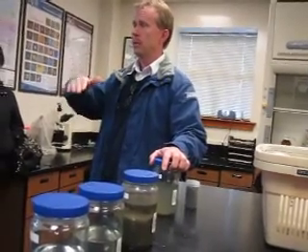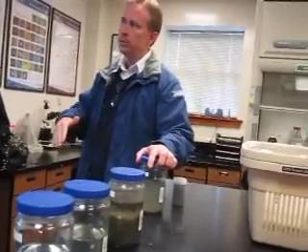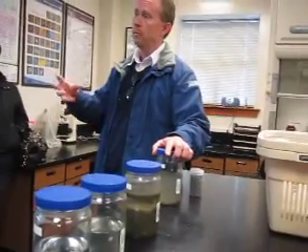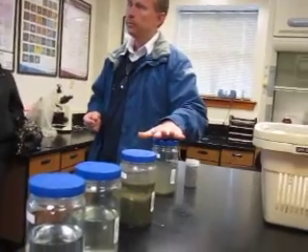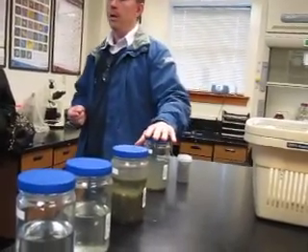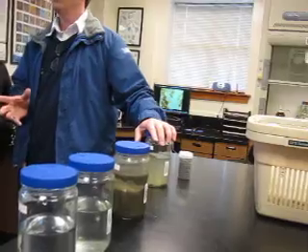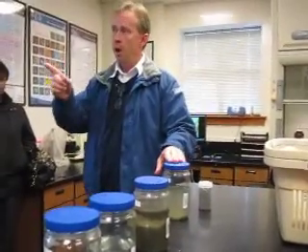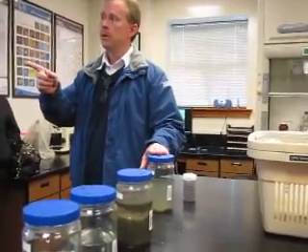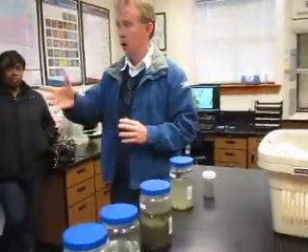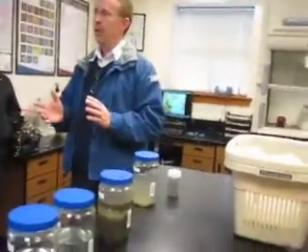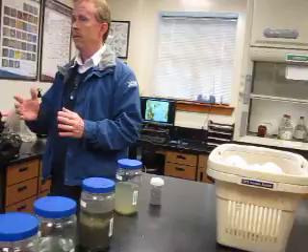As the flow picks up, it's going to pick up more samples. As it decreases, it'll pick up less samples. But it'll pull a 100 ml sample. So 5 days a week, we're always collecting samples on the influent. And on the effluent, we're only doing 3 days a week on composite sampling. But we also have an influent pH meter, which is really my operator's indicator that there may be a problem, because if that pH gets below 6 or gets above 8, they have to start collecting samples.